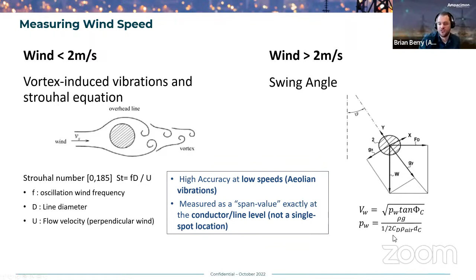So below 2 meters per second, we can measure it with that. And at high wind speeds, the conductor actually gets pushed aside. So we can measure the equivalent swing angle. And that swing angle is then used to calculate wind. I don't have the picture of it, but essentially using those two methodologies, we're able to measure wind very, very accurately.